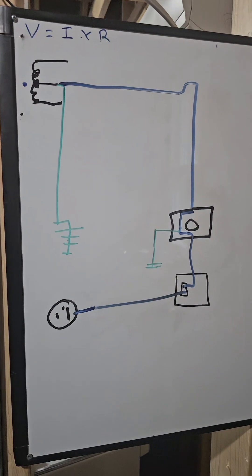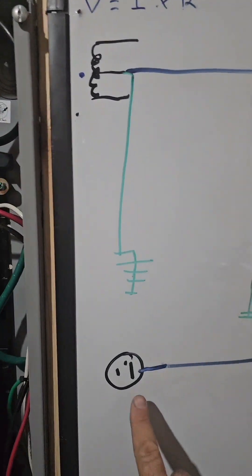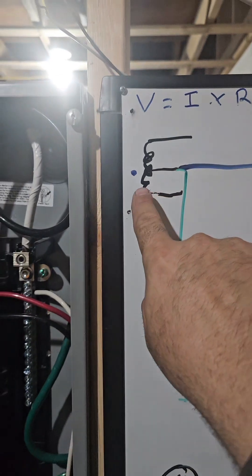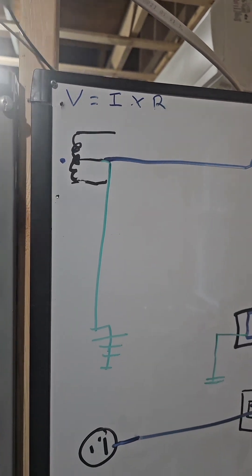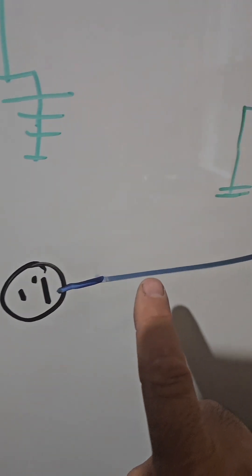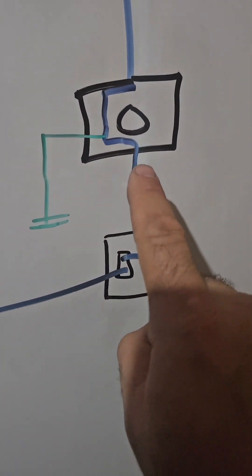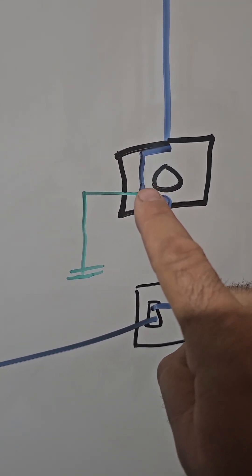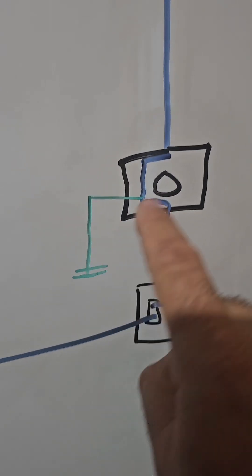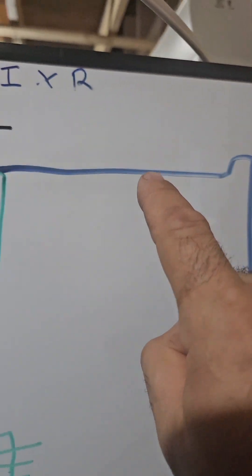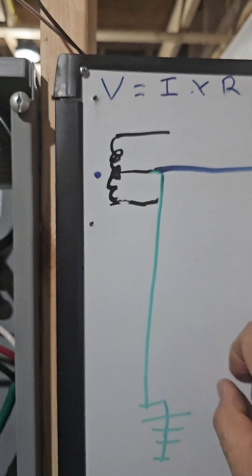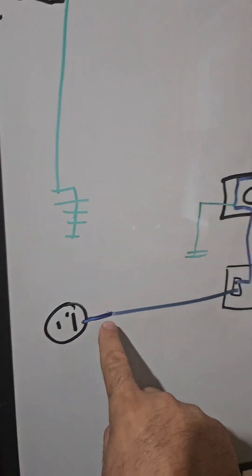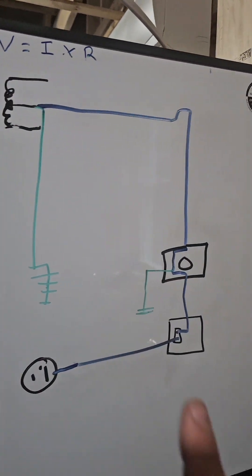Let's follow the path of that conductor. I've drawn it in blue because I can't draw white on a whiteboard. Here's the receptacle, this is your panel, this is your meter and first point of disconnect, and this is the transformer on top of your telephone pole. The white wire goes from the receptacle back to the panel, then up to your first point of disconnect where it is connected to ground rods — so it is grounded. Then it goes up through the riser of the service, across the triplex drop, to the midpoint of the transformer, where it is grounded again. So this wire is both the connection back to the midpoint and the grounded conductor.